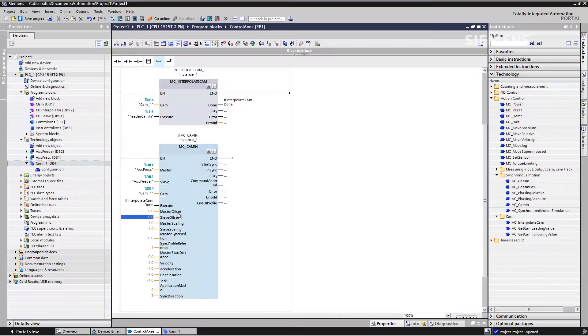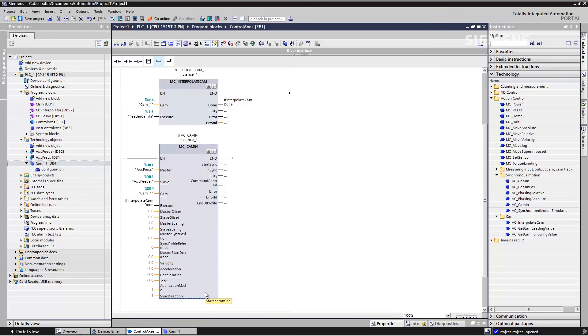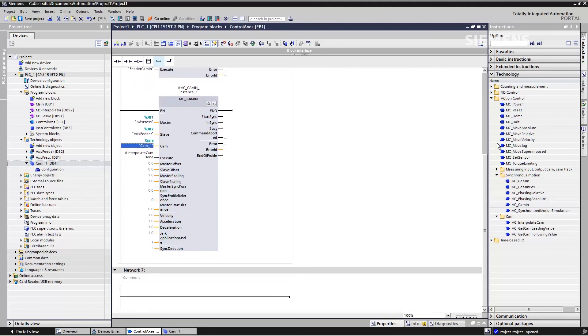For example, on CAM disk pitch 2:1, which is naturally also an option. In our case, however, we're sticking to the basic settings. The question still arises: how do we perform the coupling? This is performed either by specifying the path or by specifying the dynamics. We choose to specify the dynamics and select zero, leaving the default settings as they are. As a final step, we can specify whether the CAM disk should pass through once or cyclically — that is, when it reaches the end, it restarts from the beginning, and that's what we want to do here. We've now coupled the infeed to the press via the CAM disk we just defined. In order to stop and uncouple the infeed axis, we add a positioning command to halt the infeed at zero.